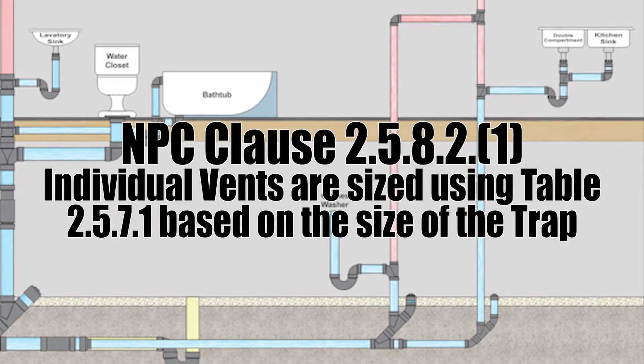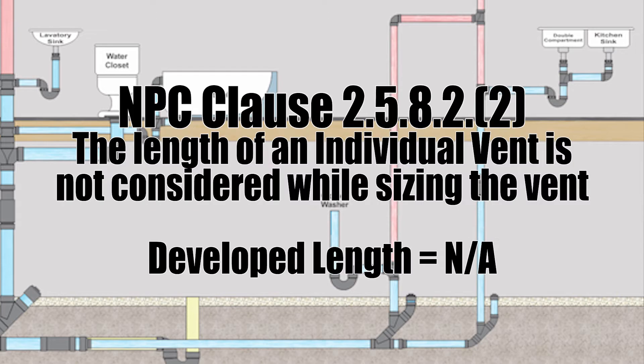Clause 2.5.8.2 number 1. The size of individual vents and dual vents shall be determined using table 2.5.7.1 based on the largest trap served. And 2. When sizing an individual vent or dual vent, the length is not taken into consideration.